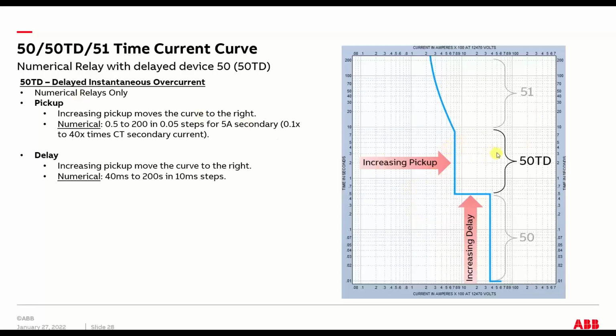One of the advances that almost all numerical relays have now is this added piece that you can add to a typical overcurrent, which is sort of a time delayed instantaneous. Some people call it a 50 TD, but it allows you to have a true instantaneous plus a delayed instantaneous, and then a time overcurrent, which is inverse time. And these set with pickup or tap, and then delay. This lets you mimic some of the features you would see in an electronic low voltage breaker, where you'd have a long time element, a short time element, and then instantaneous.